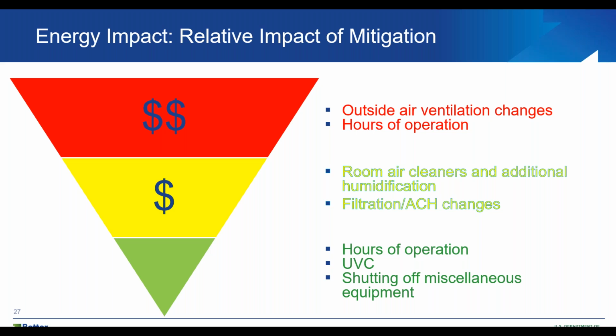And what about CO2 sensing? Do you think that's important, either existing or additional ones for the future, for making sure about occupancy levels? So CO2 sensors are a good one, depending on whether they're added into the return duct or in specific zones and averaged. Again, this is one of those that typically does not get high priority. I've seen plenty of them reading unexpected values, and they don't take a high priority. Maybe as a result of COVID, they'll take a higher priority to understand that there are people in here and you need to do something about it. So I would say that, and the fact that you see more demand control ventilation coming out, I would think that they're going to be more important going forward.